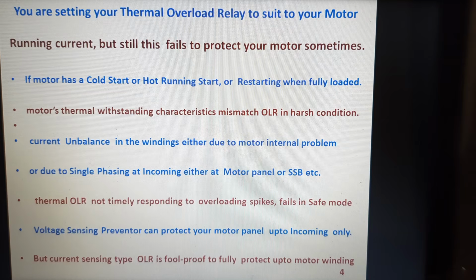The thermal OLR does not respond in time to overloading spikes, or it fails in the safe mode whereas the motor gets burnt out. Even the voltage sensing preventer that is used in your motor protection panel protects the motor at the incoming of the motor panel only, and it does not protect your motor. But the current sensing OLR type is a foolproof device to fully protect the motor up to its winding.